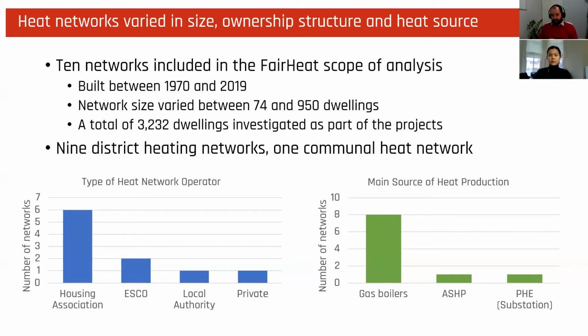Again, on scale, from 75 units, a typical communal heating system in London, all the way up to 950 dwelling units, which were big district heating systems. In total, across those 10 projects, there were 3,232 dwellings that we looked at as part of the overall project. Of those 10, 9 were district heating networks. As Joel mentioned earlier, that meant that there was more than one building connected to that heat network. In many cases, it was only 2 or 3 buildings. These weren't big district heating systems, and one of them was a communal network.